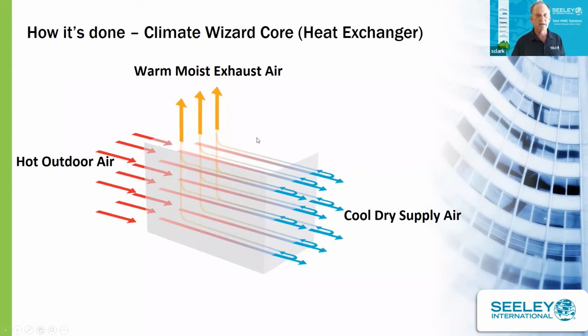exchanger part of our cooling technology, the important part, we call it our core. This consists of plastic sheets, alternating wet and dry sheets, in this heat exchanger. Basically we take the hot outdoor ambient air and run it through the dry sheets, where it's cooled down indirectly by water that we put in the top. A portion of that cooled dry air goes back through the wet sheets, is combined with water that comes down from the top, and is exhausted out of the unit as warm, moist air that's commonly known as scavenger air. Of the air that's coming in, about 55% is the conditioned air that goes to the space. About 45% is the warm, moist air.